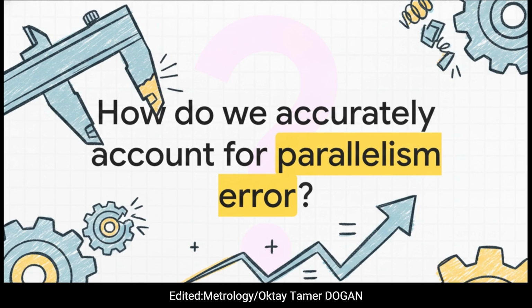How do we accurately account for parallelism error in our uncertainty calculation? If a client uses the very tips of their jaws all day, those jaws wear down unevenly, creating a wedge instead of a perfect clamp. If they formally request that this parallelism error be factored into the uncertainty budget, how does a technician actually solve that? Well, it's a three-step process to demystify it.